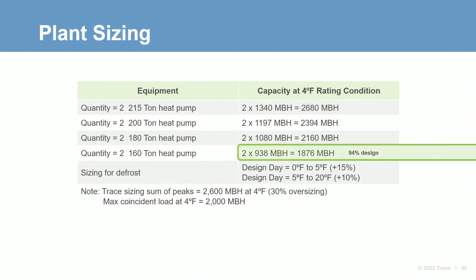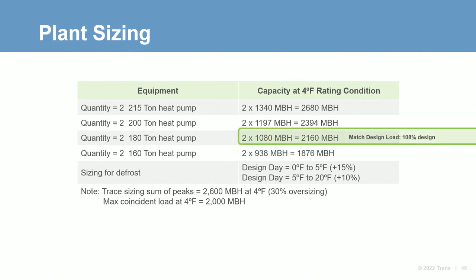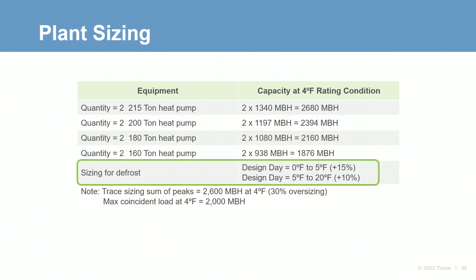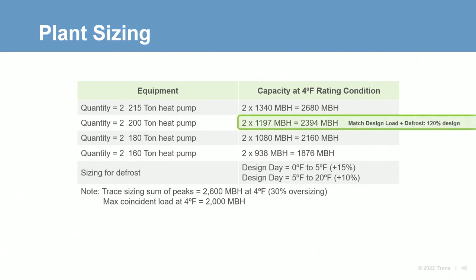On the low end, if we used two 160-ton nominal heat pumps, we'd end up at least 6% short of the design condition. The first pair of heat pumps that can meet the design condition are rated at 180 tons. However, these values do not account for defrost. Using the derate table that Dan just showed, we need to account for about 15% of the design capacity. In order for us to safely meet our heating design condition and account for defrost, we'd recommend using two 200-ton nominal heat pumps for this project.